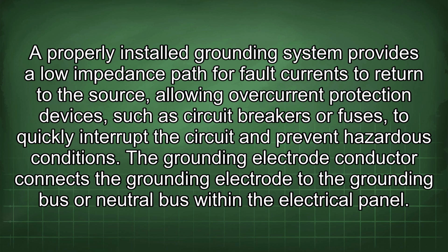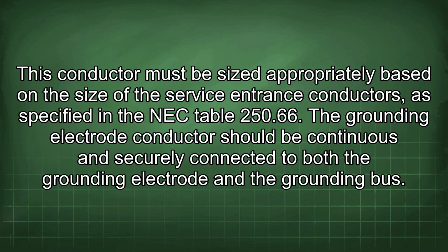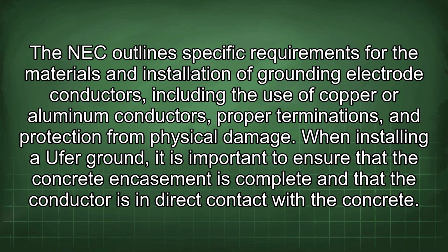The grounding electrode conductor connects the grounding electrode to the grounding bus or neutral bus within the electrical panel. This conductor must be sized appropriately based on the size of the service entrance conductors, as specified in NEC Table 250.66. The grounding electrode conductor should be continuous and securely connected to both the grounding electrode and the grounding bus. The NEC outlines specific requirements for the materials and installation of grounding electrode conductors, including the use of copper or aluminum conductors, proper terminations, and protection from physical damage.